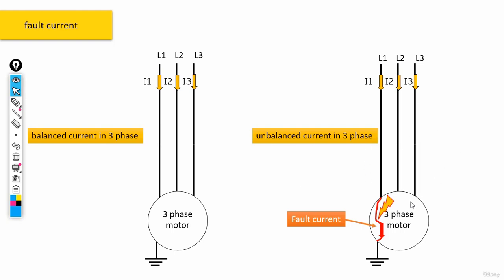Now, guys, for any sort of reason, let's say the coils and the motor itself interact with the panel of the motor and then with the earth, okay? This way, a fault current would be created. In this case, that a fault current has been created, we say that we have an unbalanced current. Now, an unbalanced current could cause the motor to overheat, and for example, this could ruin your coils completely. Now, guys, to protect our motor against these unbalanced currents or these fault currents, we actually need to use some new devices, some new equipment.